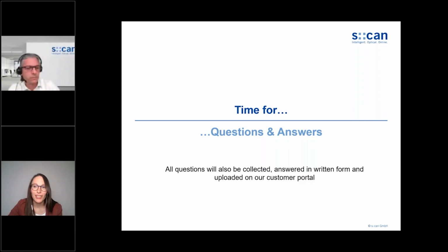In wastewater applications, are the best results in situ or by bypass installations? If you ask me, I would say in situ applications, because by taking a sample out of the water and pumping it, you already start to change the composition of the sample. For instance, a pump will not collect all the solids that are present in the wastewater.